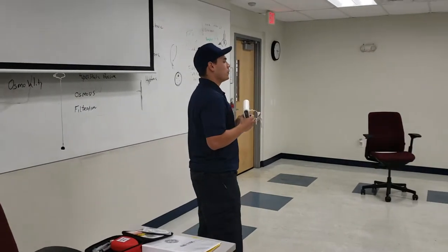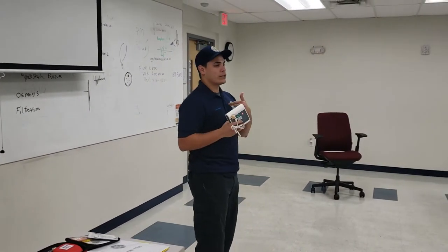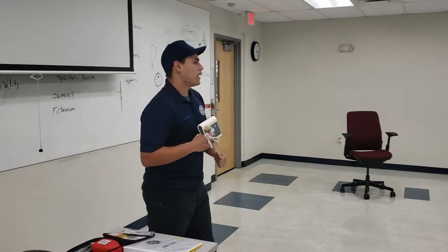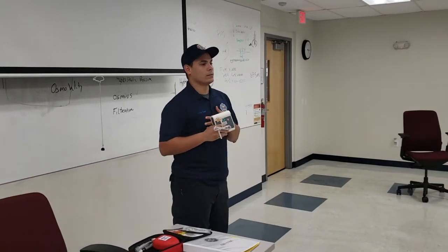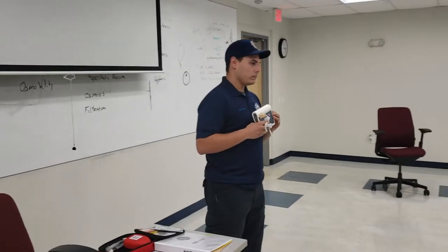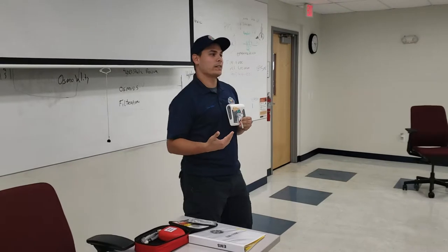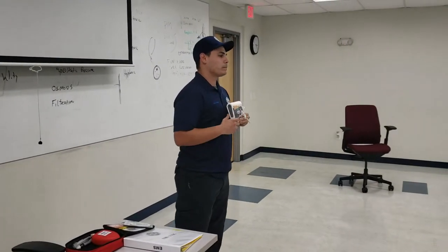While it's analyzing, you are not going to touch this patient. You don't want to touch this patient because it'll then analyze your good heart instead of the patient's bad heart, okay? And then it'll get a wrong analysis. Do not touch the patient. If you forget, it'll remind you.